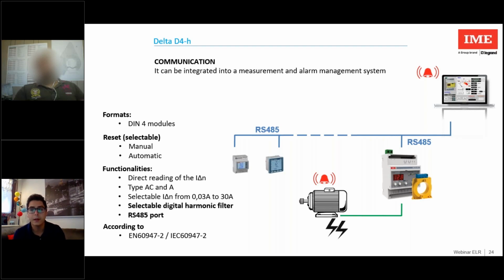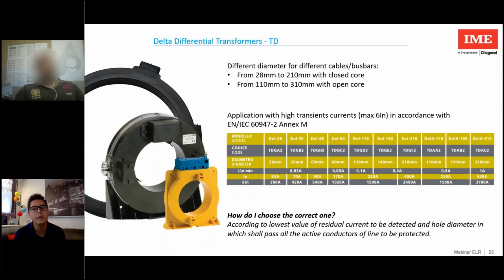To detect the differential current, there is a toroid. This toroid has different diameters for different cables or busbars. We go from 28 mm to 210 mm for closed core toroids, and 110 mm to 310 mm for open core toroids. Each toroid is characterized by a nominal current and a minimal detectable differential current value. According to EN 60947, in applications with high transient currents, I can take as reference 6 times the rated current.